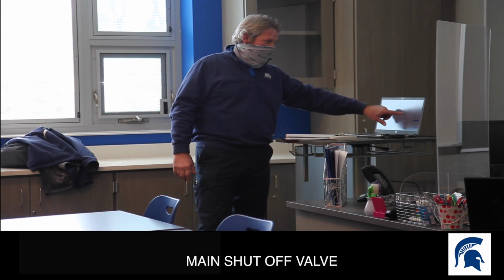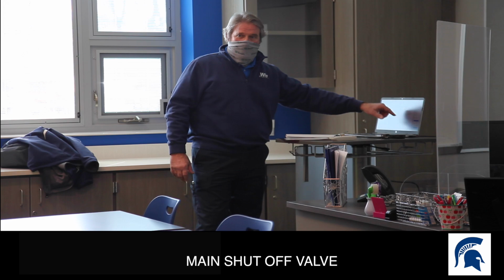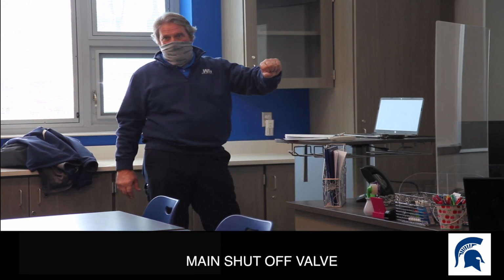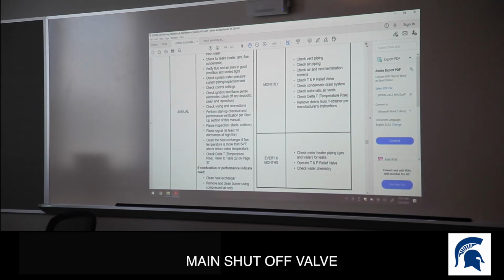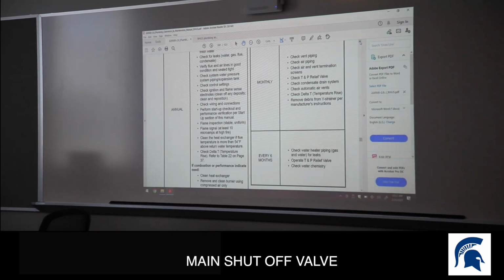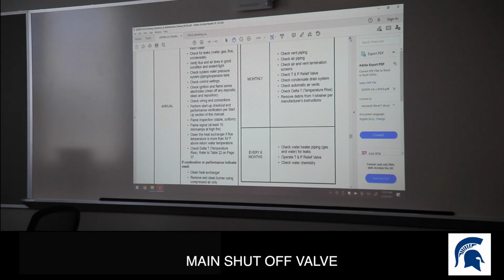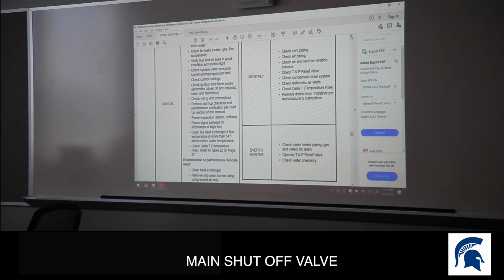And that's what they talk about, the temperature rise. And the only way to check that is on your incoming water temperature and your outgoing. You've got to put a thermostat on there, check the temperatures. And I have a sheet here. I'll give that to you. It'll show you it's in here as well.